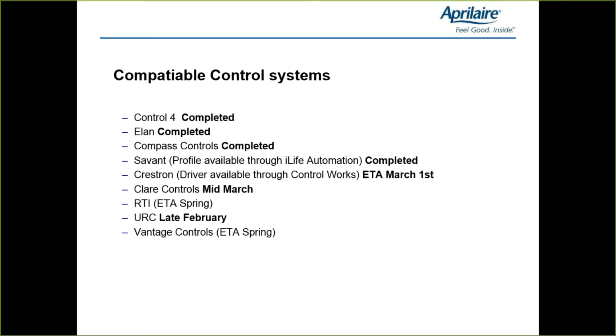Again, we appreciate your time. It looks like there's one other question that might come up here. So with an Elan control system in mind, can the 8820 be used for heat only, as in a garage? Yeah, you can set our thermostats up to just control heating. I'm not sure what the Elan user interface will look like if they take away the cooling and humidity set points, but absolutely our thermostat, as long as you've got a common wire to power it up, we can control a heating-only system. And as the Elan rep, I can tell you that in the programming interface, you'll just have a heating portion, not cooling, so it won't even show up on the Elan interface.